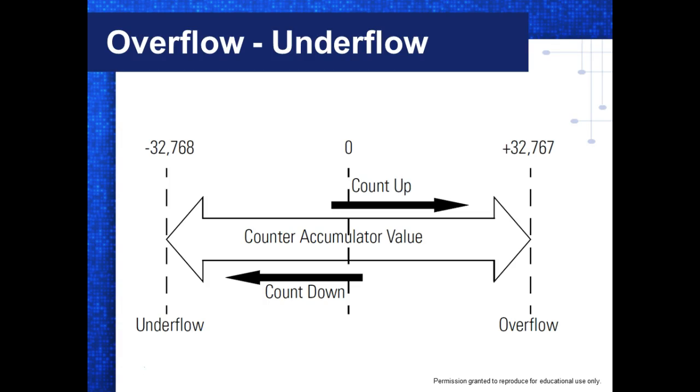So if you know you're going to count over that, you need to take care of it with your program. When the counter hits its preset, what's it going to do? It's not going to stop. It's going to keep counting until you reset it. That's up to the programmer, not up to the counter. The counter's never going to lose counts.